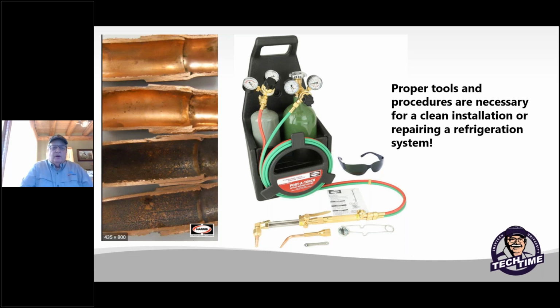So eventually all that soot and stuff from your welds flows through the system, and hopefully it's all caught by the filter dryer before it gets into the expansion valve or the suction filter. So again, more contamination just makes the longevity of the compressor a lot less. So use the proper tools. Cleaning of the system up is imperative when you are replacing a compressor.